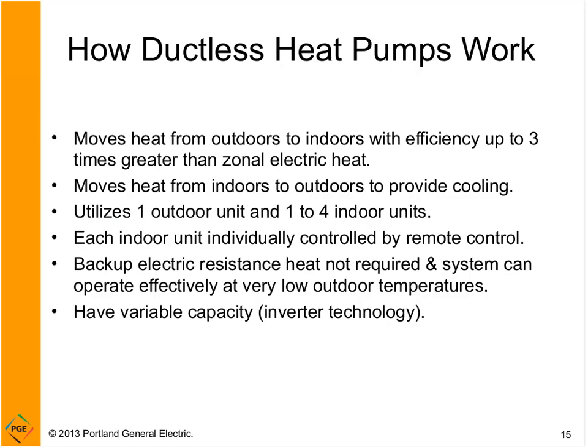A little more specifically on how ductless heat pumps work. Ductless heat pumps move heat from outdoors to indoors with efficiency up to 3 times greater than zonal electric heat. They move heat from indoors to outdoors to provide cooling. Generally, they use one outdoor unit, and then you can use anywhere from 1 to 4 indoor units. And I'll talk a little bit more about installation strategies in some of the upcoming slides, but there are different configurations that you can choose when selecting ductless heat pumps.